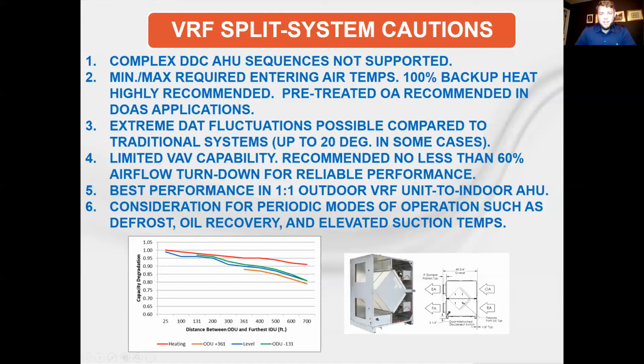And then on the DOAS, or if we look at the discharge air temp fluctuations, keep in mind when you're applying this to, let's say, a data center or even healthcare, a lot of times the discharge air temp varies plus or minus 2 or 3 degrees, and people might start noticing that. So VRF is probably not the best application for something that needs that level of control. Finally, another big one is the VAV capability. We recommend, for really reliable performance, no less than about 60% airflow turn down. There are cases where it will work with more turn down, but from experience so far with the current technology, that's where you'll be safer. And constant volume is obviously a better bet if you can do it.